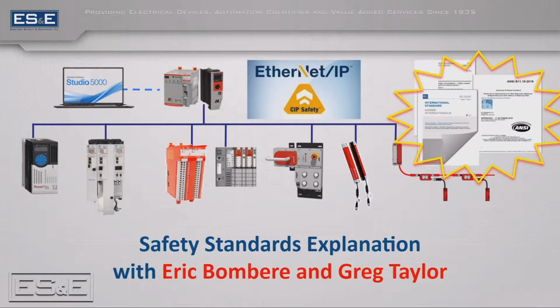But the moment we start introducing electromechanical devices like solenoids and contactors and relays and stuff, there is no such thing as a SIL rated contactor. We have to do a mean time to dangerous failure calculation on it. And so it's going to kind of pull us back into the performance level methodology. Most of the time we see that a lot more predominantly in the process side of things.